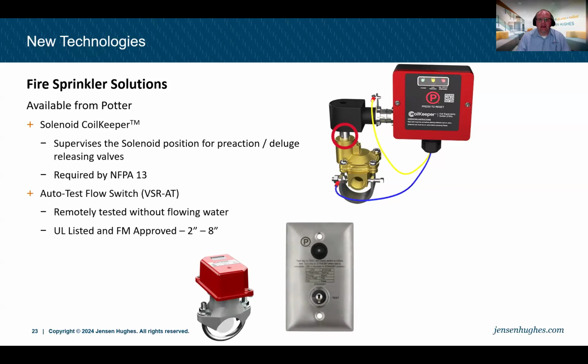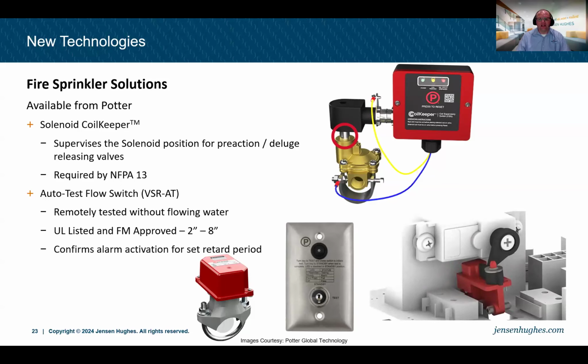This can be a really neat way to test the accuracy of your flow switch without ever wasting water or dumping water. Very handy for fire alarm technicians to be able to do this test without affecting or dumping water in a facility. So, really neat technology. And it confirms the alarm activation for the set retard period. So if we have, let's say, a 45-second delay on our water flow, it's going to test and we can measure exactly what that retard time frame is. Very nice for AHJs and inspection, testing, and maintenance folks to be able to test that ability.